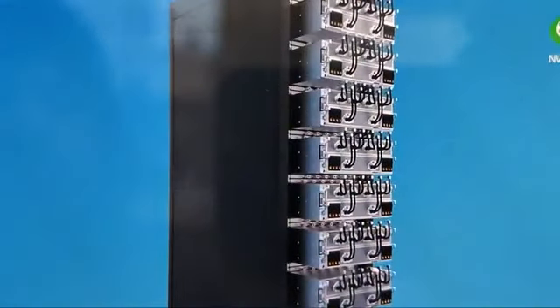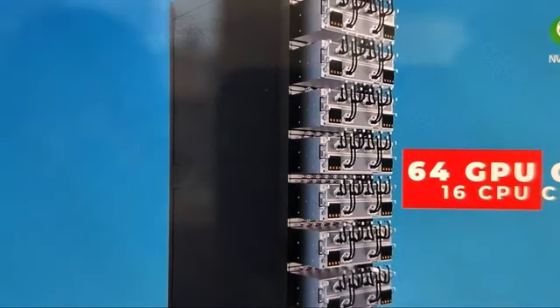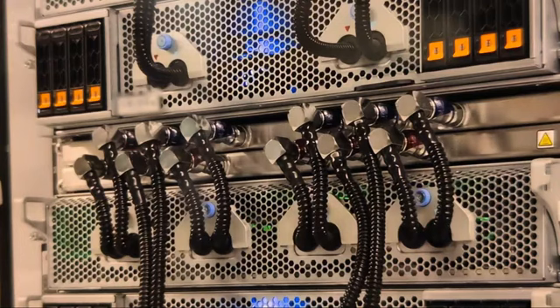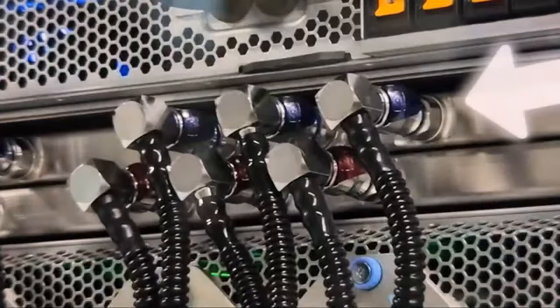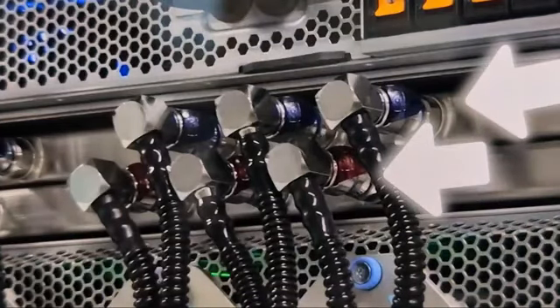There are 8 of these racks built into one cabinet with a total of 64 GPU chips and 16 CPU chips in every vertical stack. Each of the racks has its own independent water cooling system with small tubes that lead directly into the GPU housing, blue tubes for cold water delivery, and red tubes for hot water extraction.